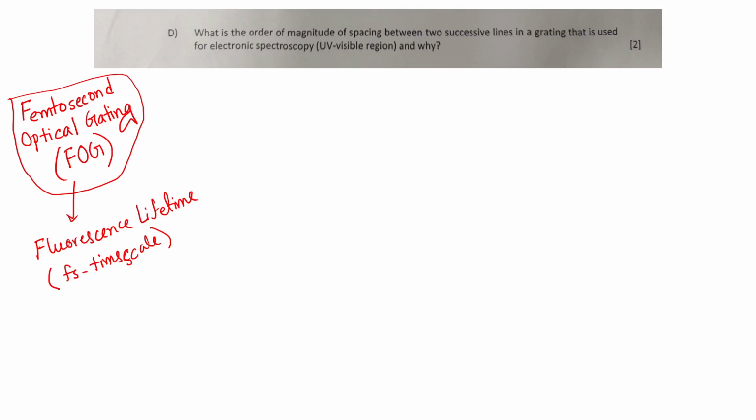If you use a capacitor and other electronics, it becomes picosecond, even if you are using a 100 femtosecond ultrafast laser. So if your compound is very weakly emissive, or even highly emissive but has a very fast component on the femtosecond scale, that can be missed in that instrument because of the resolution. There you require this FOG kind of instrument, or pump-probe spectroscopy, where you can use the femtosecond time scale. And for these you require that delay stage.